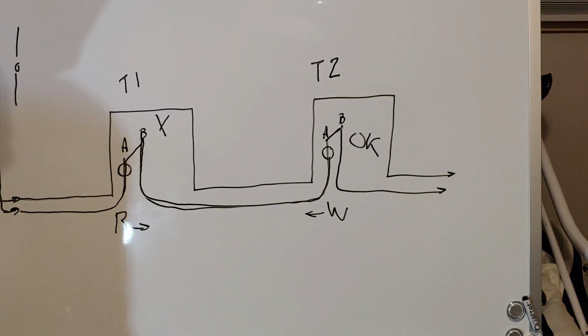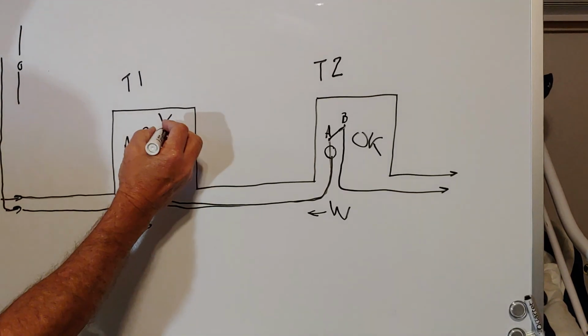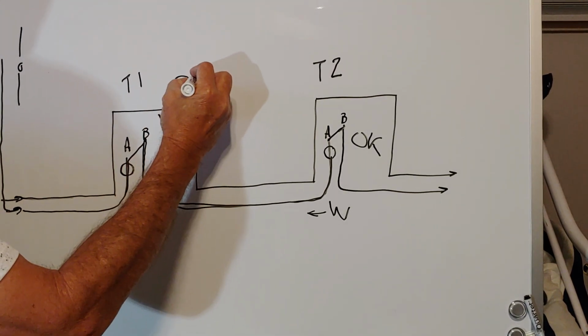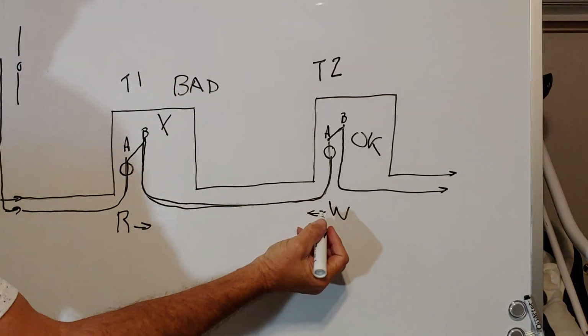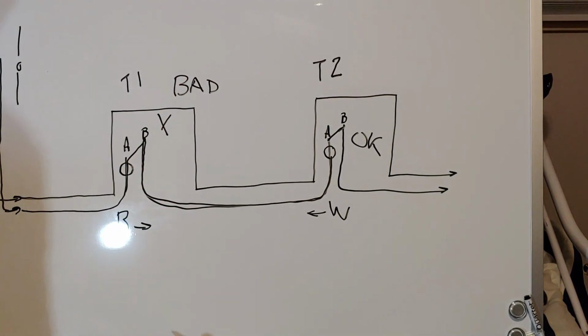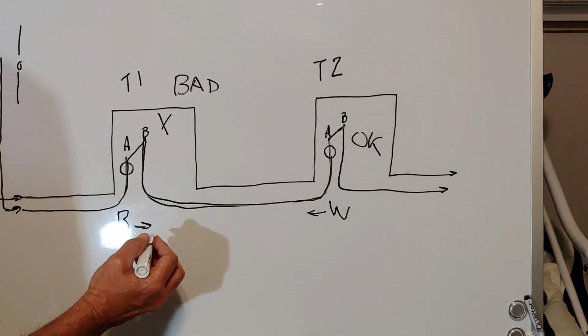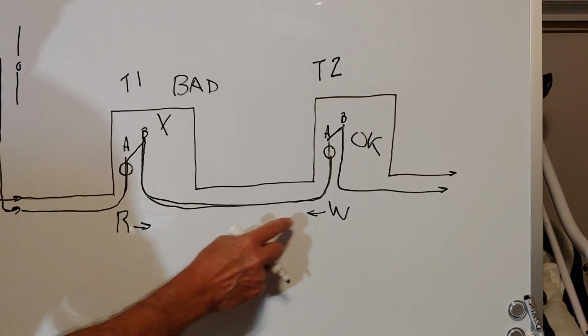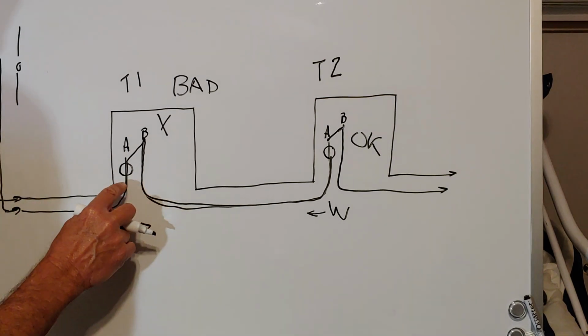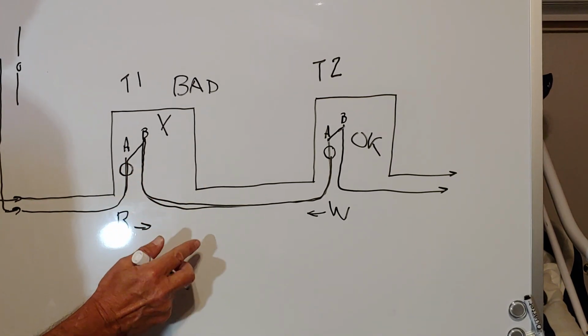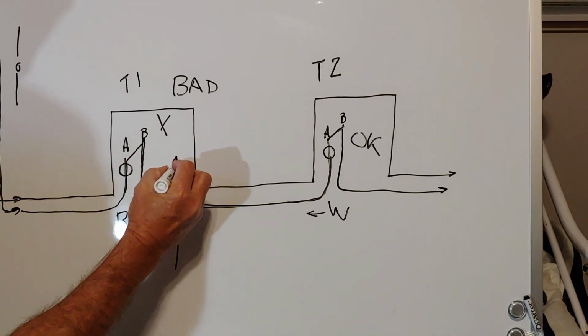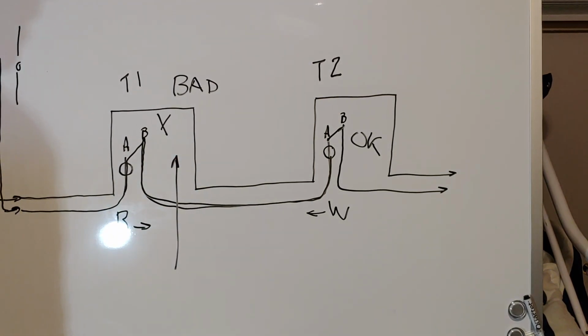So what would happen in a case where the transformer is bad and I have a red and white indicator? Now this is rare. Typically it's going to be the cable itself that's gone bad, or something's dug into it, or some kind of situations like that, or the cable is just old and faulted out. But here's what's going to happen. You're going to come in here and you're going to see red and white and think to yourself, it is somewhere in this span. Keep in your heads, it might be the transformer. Maybe. And here's how you're going to find out.